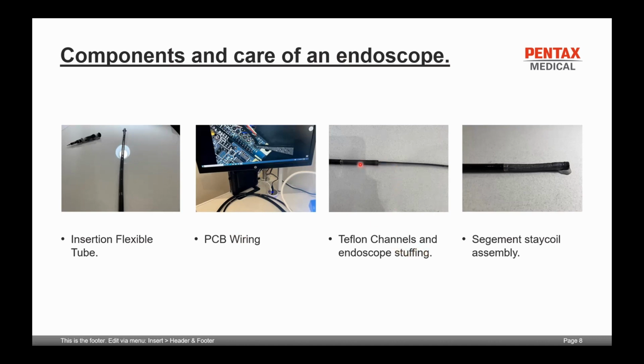This is an endoscope that's in process of stuffing, and as you can see there, you've got your Teflon channels and all your stuff that is going to be inserted into the insertion tube. And this is what we call a segment stay coil assembly. As you can see, it's a braided wire. Underneath the braided wire, again, is another coil pipe that houses everything internally, and the distal end seats up against the segment stay coil assembly.